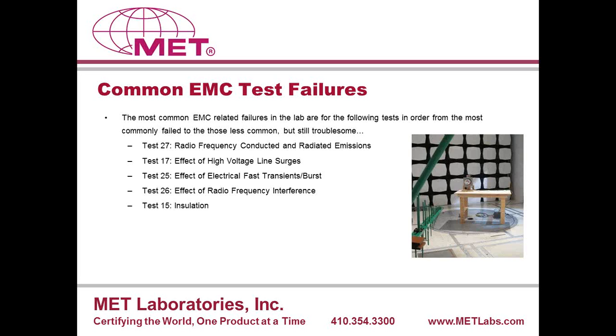The other test that we see failures on is effect of radio frequency interference, which is test number 26. So basically this is a radiated immunity test wherein the meter is subjected to a radiated electromagnetic field at a level of 15 volts per meter. And what we are doing is monitoring the display to see that there should be no deviation in the watt-hour energy reading that is being displayed. And if there is any change in that reading, it should not be more than one least significant digit. So typically the failure we would see on that test is that the reading just continuously fluctuates and keeps on increasing as we go through the test. So that is something that we would see on that test.